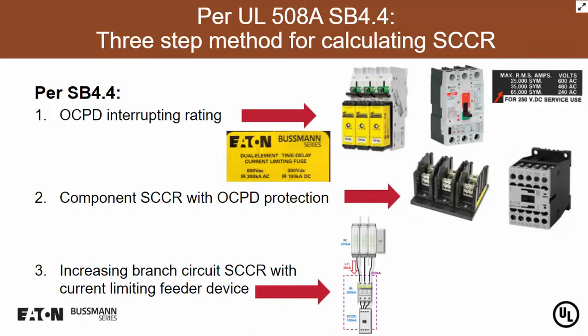And that's a combination rating, just like we would have with a power distribution block if it's protected with a fuse or a circuit breaker. So we want to make sure step number 2 is taking the components along with the associated overcurrent protective device to boost that rating up from the default rating itself. And then finally, step number 3 is taking a current limiting feeder device to increase the branch component rating. So for instance, if we didn't have a combination rating with this contactor itself, and the contactor is at the very bottom, like I'm showing, that contactor is rated for 5,000 amps. But I can increase that 5,000 amps with a current limiting feeder device, as long as the Ipeak of that current limiting device is less than, in this case, 5,000 amps.